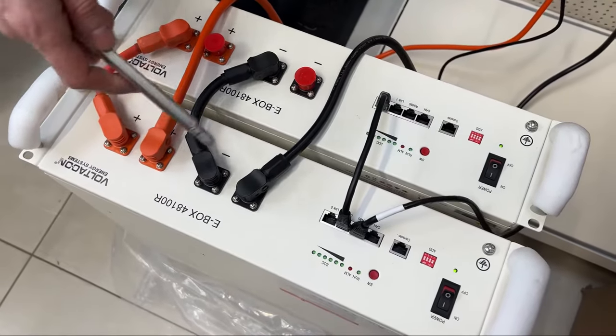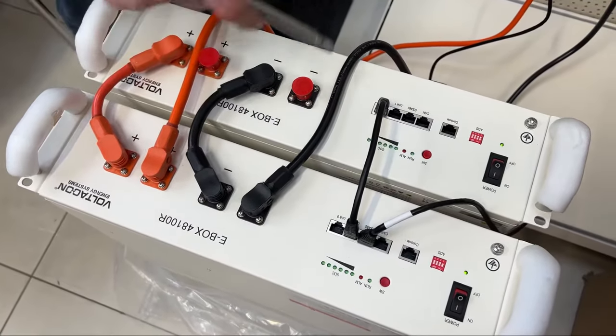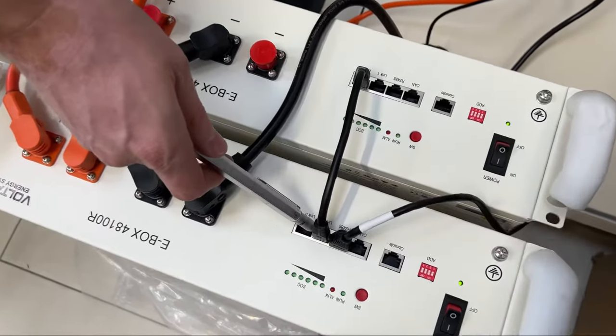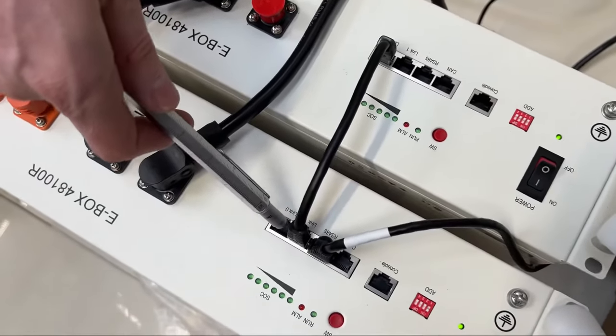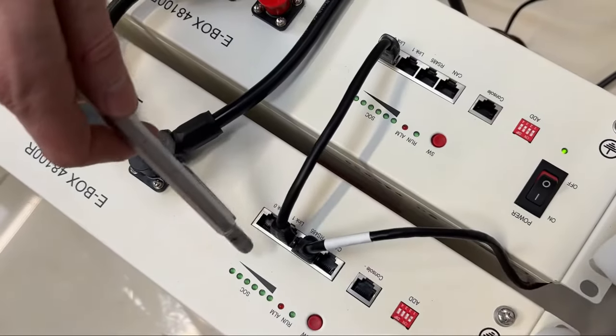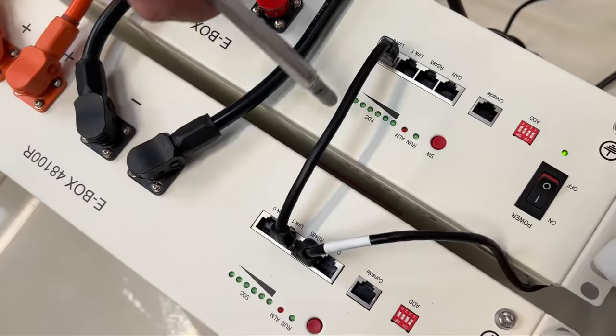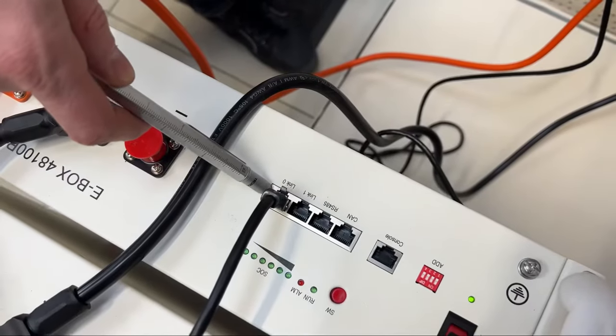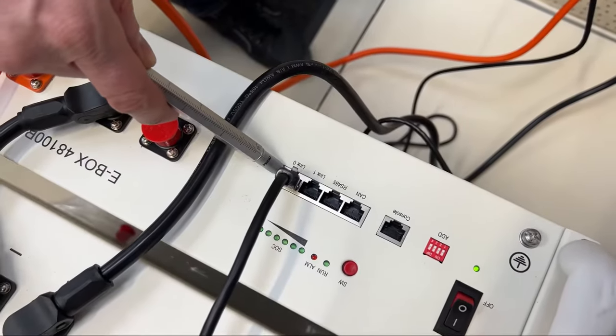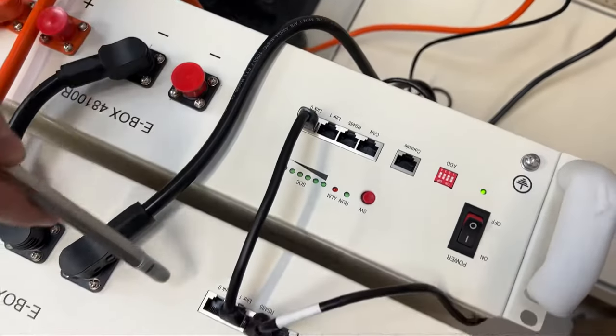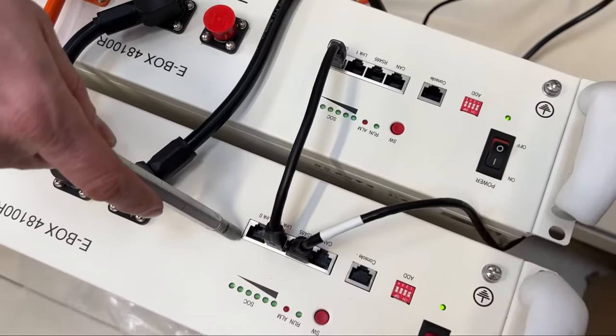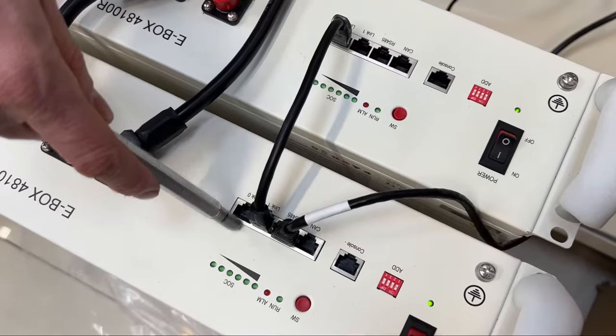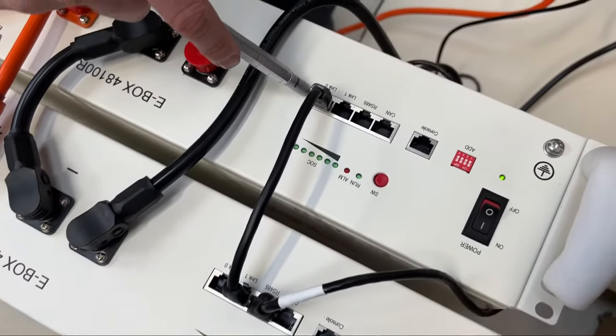When you link batteries together you have to use link 1 port from the master battery to link 0 for the slave battery. So that's always the one on top is link 1 and link 0.